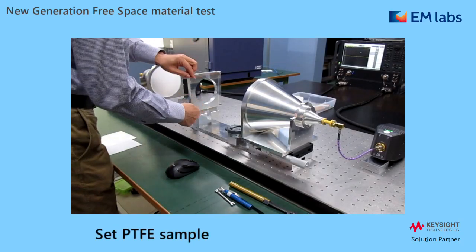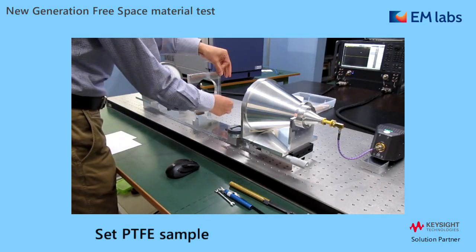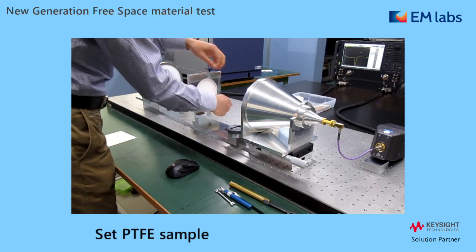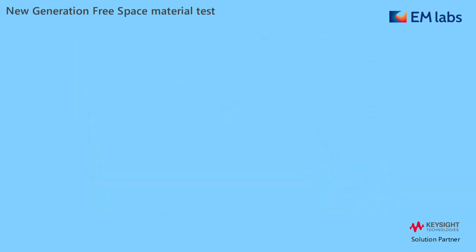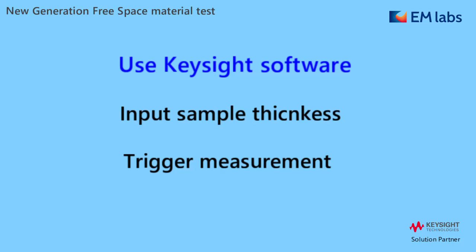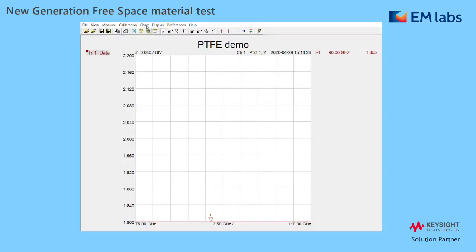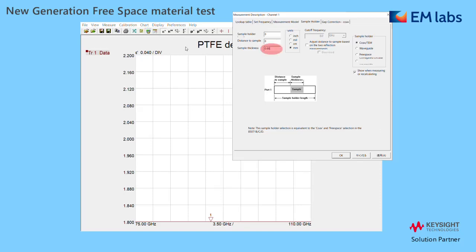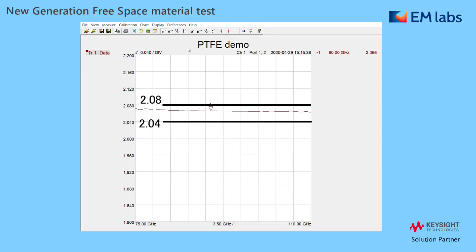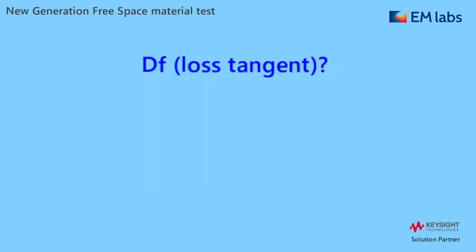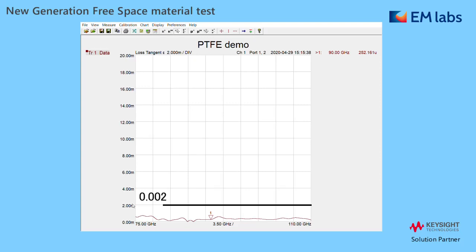Now we're ready to measure PTFE. First, set the sample. As we already calibrated the system, we just insert the sample into the holder — that's all. From here, we only use the Keysight material test software. You simply input the sample thickness — 0.98 mm — and trigger the measurement to get the results. The DK result is 2.06, as expected. For DF, it's nearly zero; if you set the scale properly, you can confirm it's less than 0.002. Much more precise evaluation is now available with our free space solution.